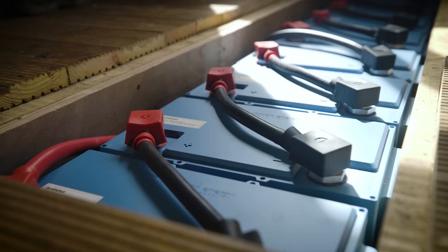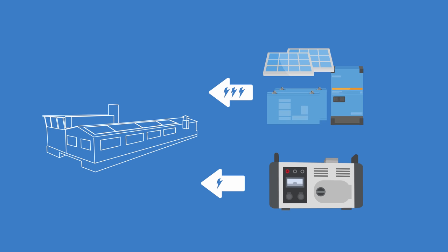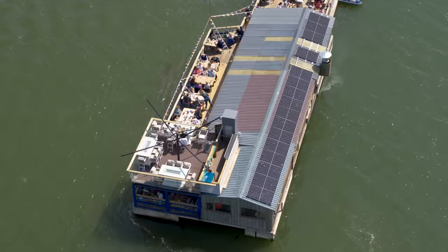The newly installed system features a 15 kVA MultiPlus 2 and 32 kilowatt hours of Victron Energy lithium smart batteries. The idea is for power to be provided by the batteries and inverter to reduce the carbon load and the load on the generator 24 hours a day. The system has been designed to handle standby loads and some peak loads, with plans over the next 12 to 24 months to reduce the cafe's load further and build the system to work with that appropriately around the clock.